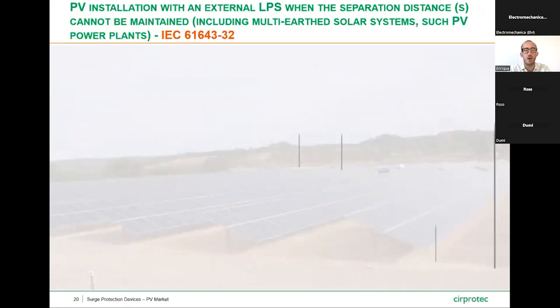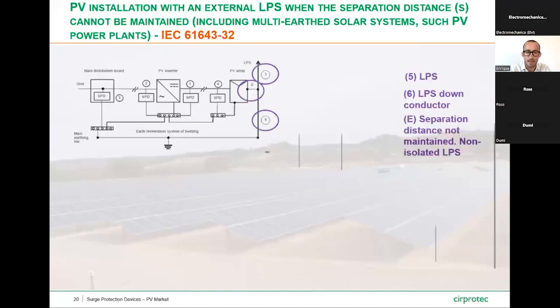Now we'll check together the last PV installation type according with the IEC. This one is with an external LPS when the separation distance cannot be maintained, including the multi-earth solar systems such as PV power plants. In that case, we do have the same LPS as before, and in the 6th location, the LPS down conductor, represented by the letter E, the separation distance not maintained, which means that we are in front of a non-isolated LPS.